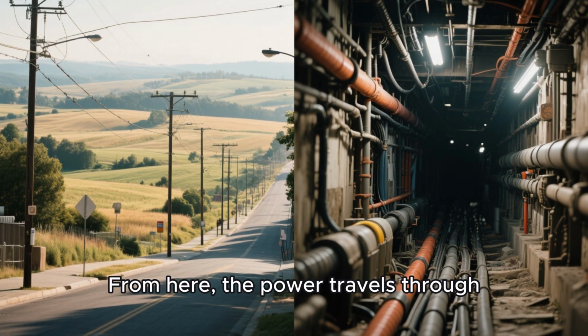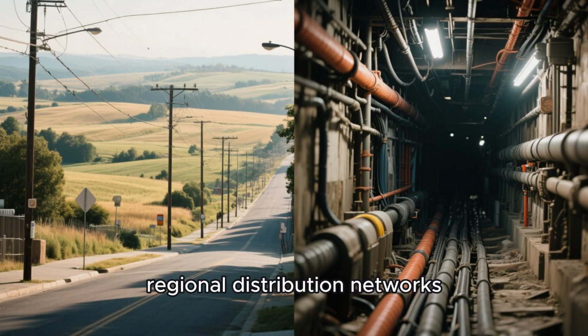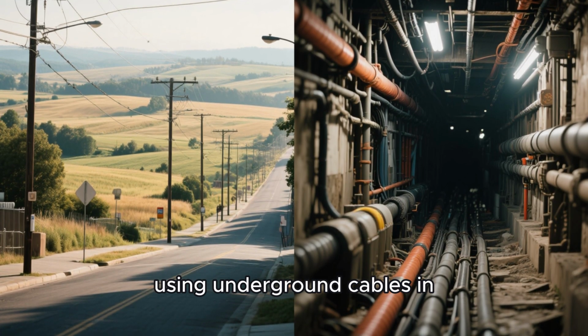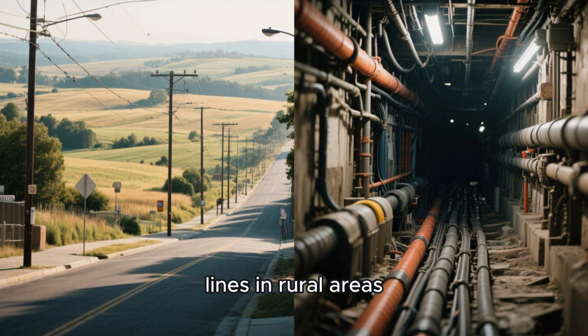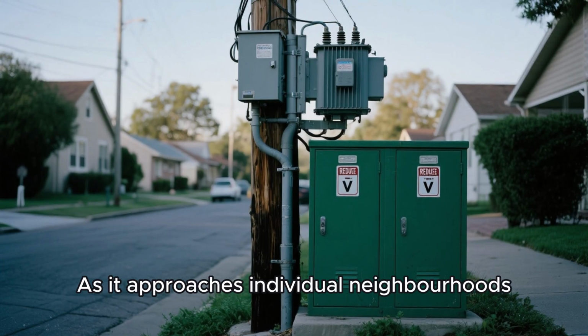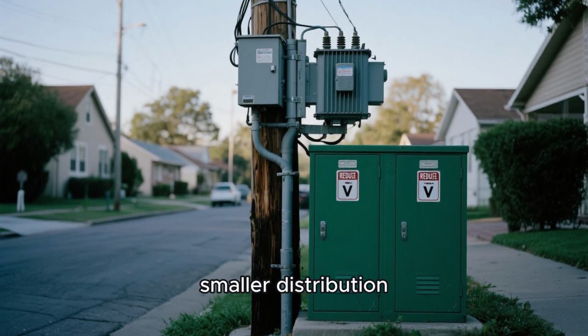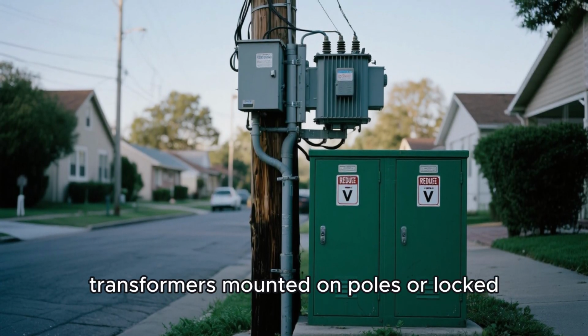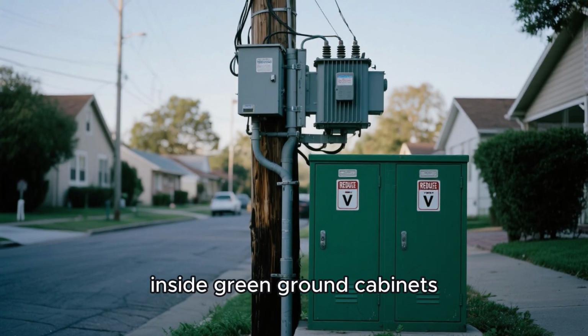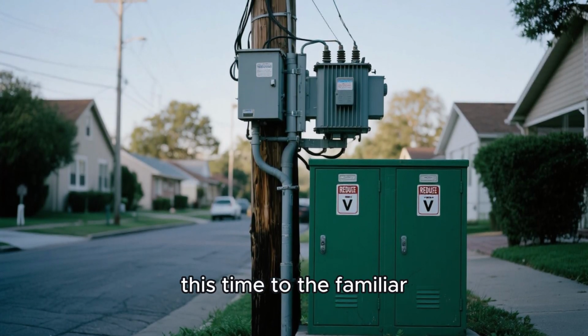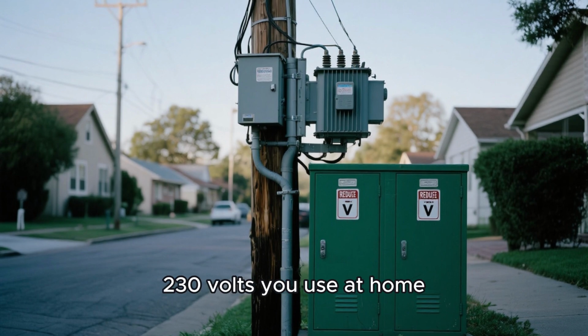From here, the power travels through regional distribution networks, using underground cables in cities and overhead lines in rural areas. As it approaches individual neighborhoods, smaller distribution transformers mounted on poles or locked inside green ground cabinets reduce the voltage once more, this time to the familiar 230 volts you use at home.